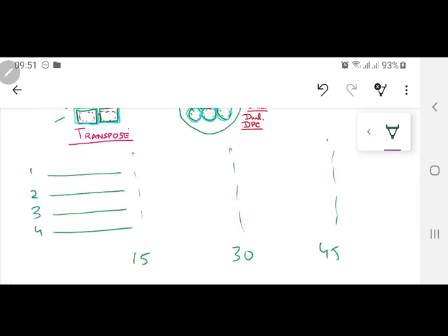Now the first conductor is at this position, second conductor here, third here, fourth here. After every 15 conductors, or 1/4 of the winding, you are going to change the position of your conductors. Now this is just an example. This 15 can be very small as well, it can be large as well. I've just taken an example that there are 60 turns in the whole length of the winding, and in that whole length conductor number 1 and conductor number 2 take the topmost position, and afterwards conductor number 3 and conductor number 4 can take it.